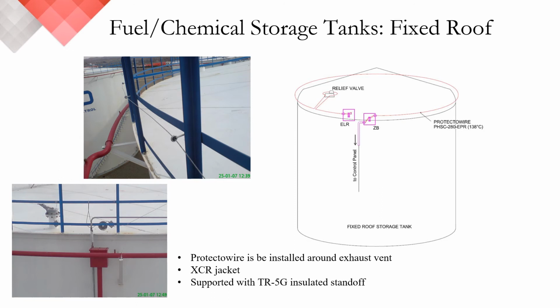As you can see from the illustration, the linear heat is applied around the perimeter of the storage tank and around the relief valve. The end-of-line resistor, shown at the top of the tank, can also be positioned to make annual tests more convenient. The beauty aspect of linear heat is its simplicity in commissioning and in its annual testing. Per NFPA, linear heat is classified as a non-restorable fixed temperature device. As such, all that's required to commission or test is to short the detector at the end of line.